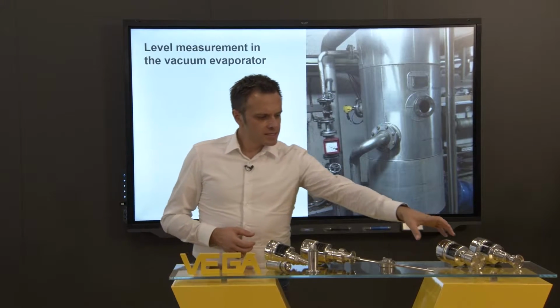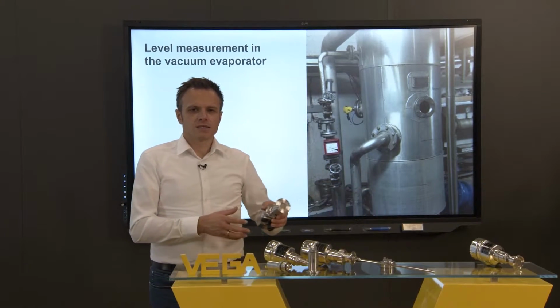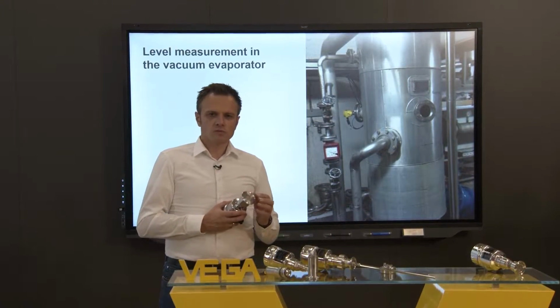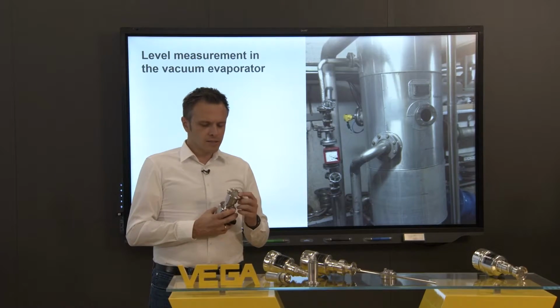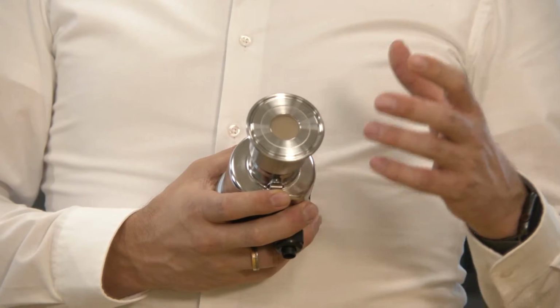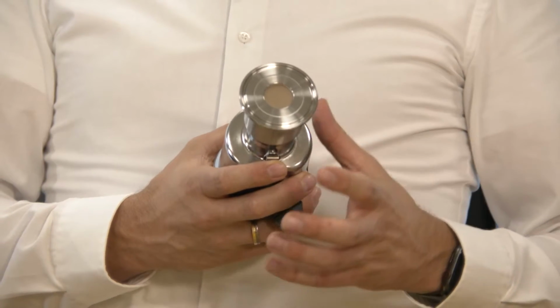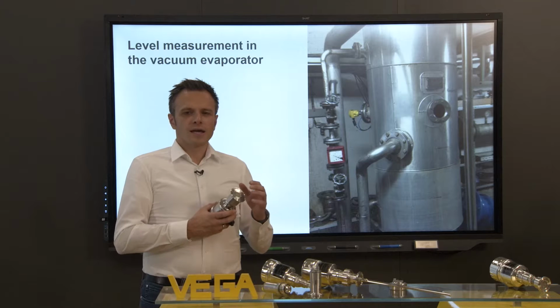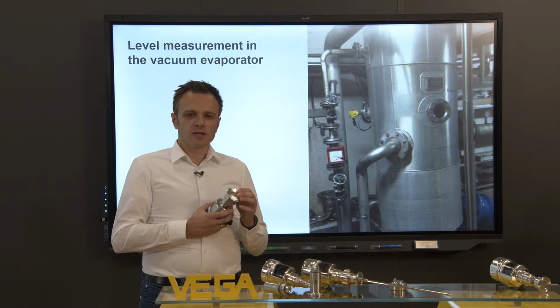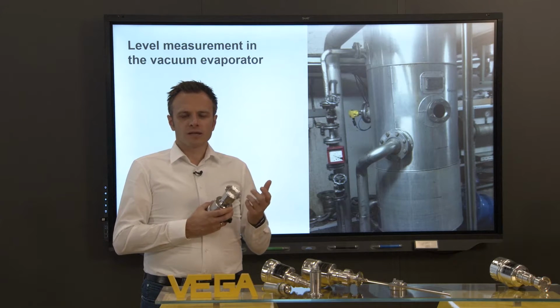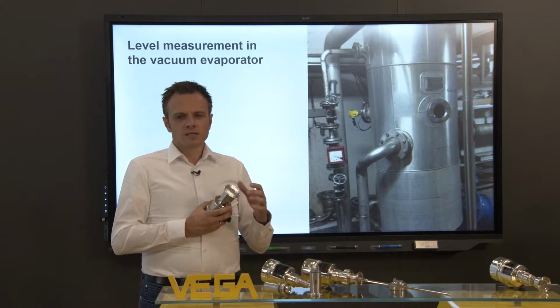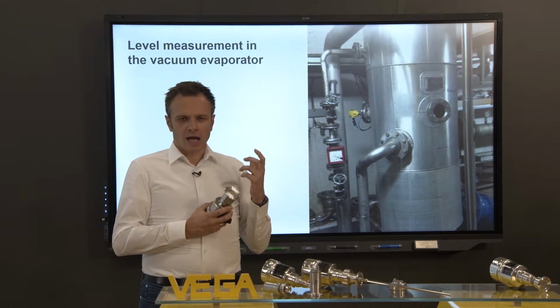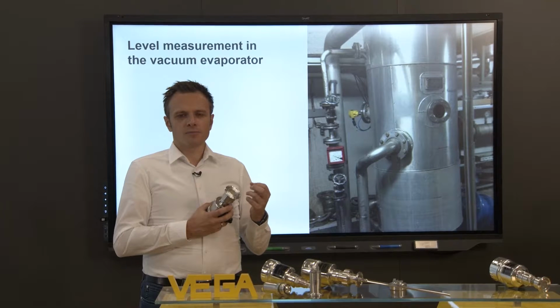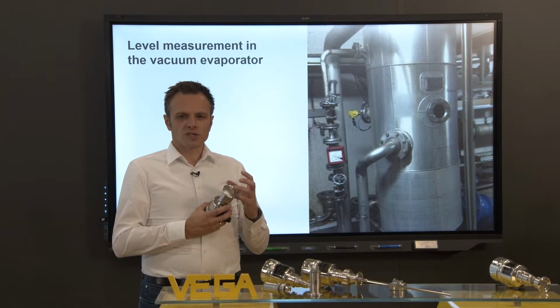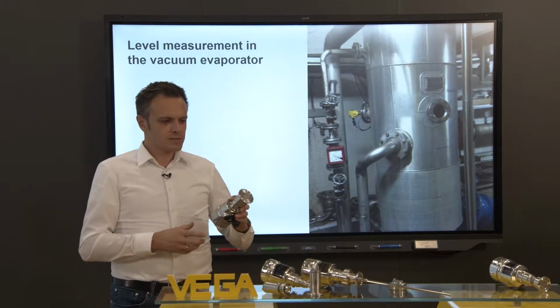When you use a ceramic sensor in that case, the VEGABAR 82 with a ceramic cell, then you can go with the ceramic cell as a dry measuring cell. You can combine two sensors to an electronic differential pressure, and the dry measuring cell has no oil filling. So there is no liquid inside that can boil. So with that measurement, you have a high reliability under high temperature and low pressure. So it's a really clever solution.